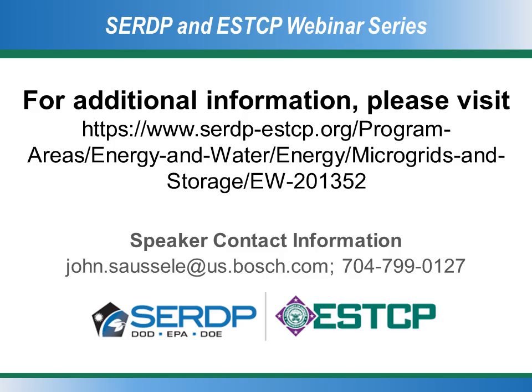Very interesting thing, they found another piece that we didn't anticipate that is significant. When you have energy losses through AC to DC conversion in lights specifically or any devices within the building, that loss is basically going into heat. So they pointed out and they modeled that heat is being generated into the building, and then that heat has to be removed by the air conditioning system in summer. So there's actually a multiplicative effect of reducing the losses because we also reduce the air conditioning load. And they actually modeled that across the U.S. and showed that there was an additional advantage to a DC system in areas that had especially heavy air conditioning loads.